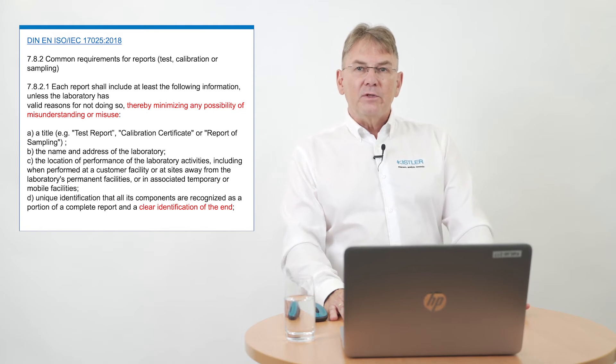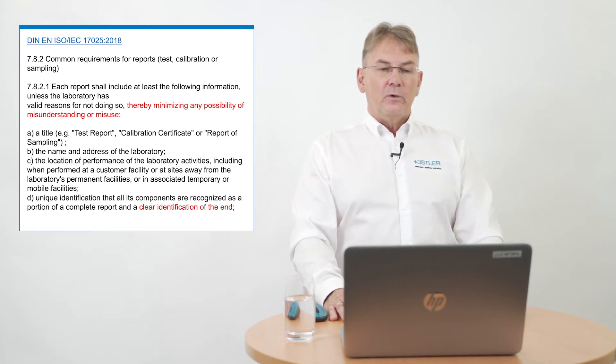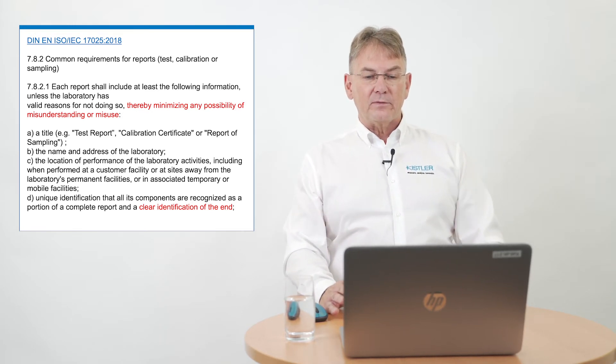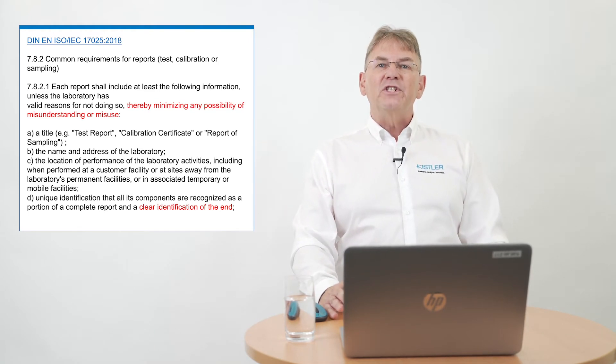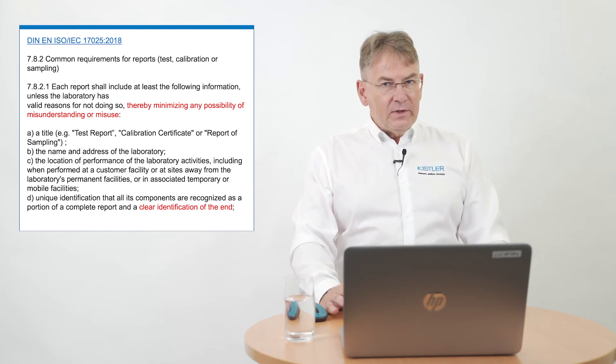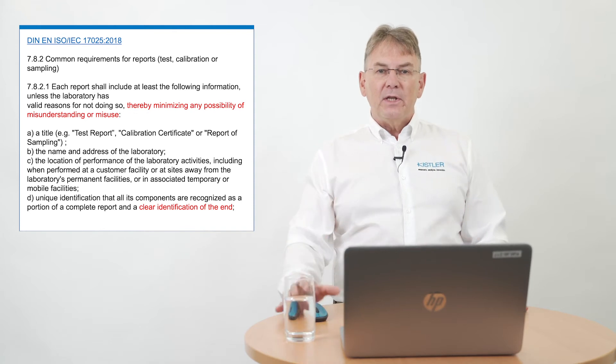Something else I want to point out is the date of issue of the report and the identification of the person authorizing the report. Something you may overlook is actually a big change. In previous calibration certificates, you could expect a signature from the laboratory. Right now, ISO 17025:2018 requires in section 7.8.2 the identification of the person authorizing the report. That means you find nothing more than just a name — possibly of the laboratory leader or his deputy. No signature is needed anymore; just a printed name is fine.